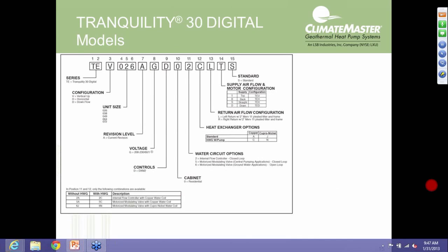For instance, if you were to put an open loop version on a closed loop application, and to get your closed loop type of flow rates that we're usually trying to achieve, there is significant pressure drop through that valve. And it'll probably drive you to adding another pump on the system needlessly, just because of having the wrong unit for that application. So the two should never be interchanged from one another. So if you're doing open loop, you order the open loop version of the modulating valve. If you're doing closed loop and you want to use a modulating valve with an external flow controller or doing central pumping on that type of application, then use the closed loop version of the modulating valve.